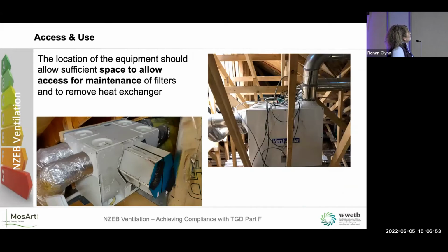Access and use then. The location of the equipment should allow sufficient space for access for maintenance of filters and to remove the heat exchanger. So you can see over here on this side, this vent access unit, somebody installed it right beside the timber member there, and that's where your filter is, so you can't actually get at that filter to change it. I was doing this one time in class, and the fellow who actually installed that was sitting in the class, and I asked him why, and he said the timbers weren't there when I put it in, but I don't believe him. Nobody is going to take a saw to the structural timber in the roof just to change a filter on an MVHR. A lot of the machines now, if the filters get so clogged, will just shut down and won't work at all.